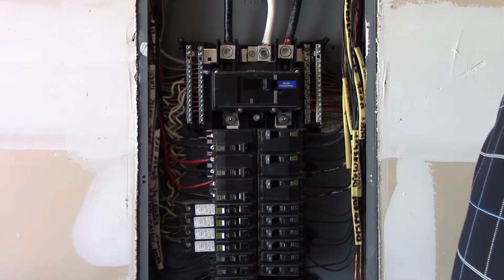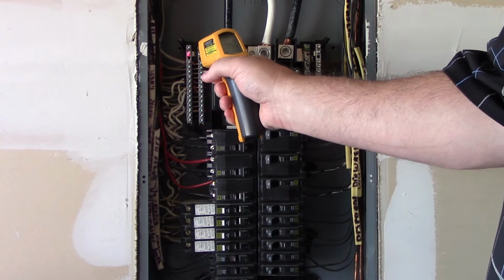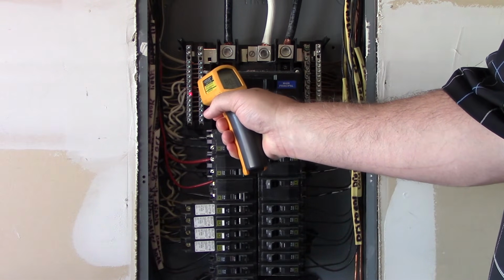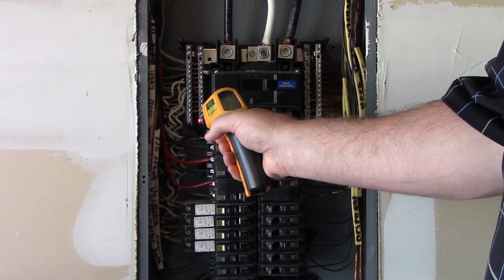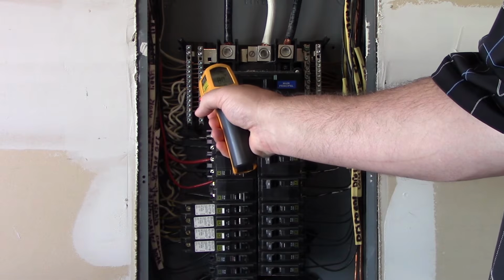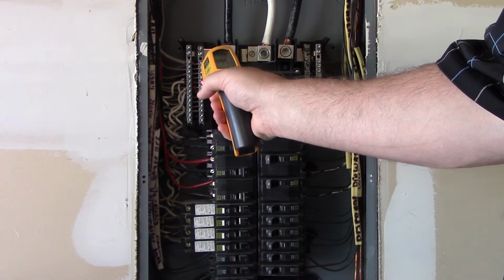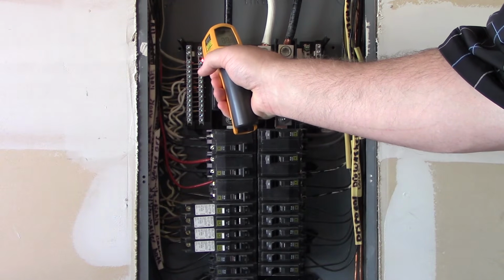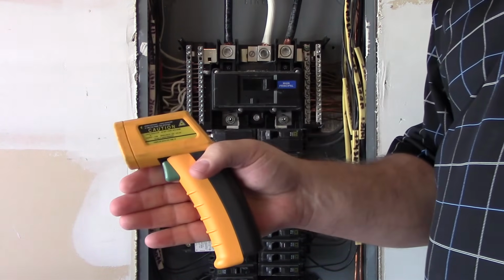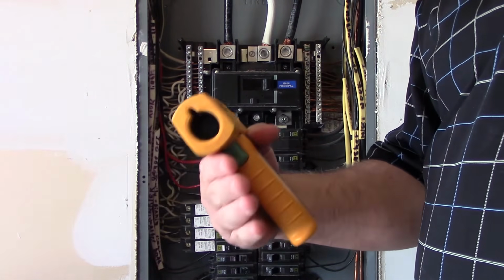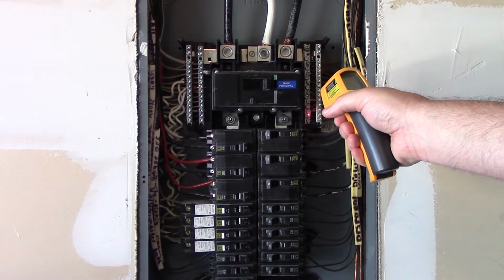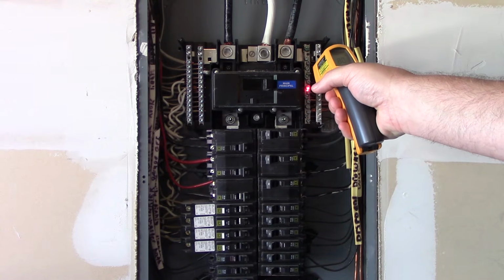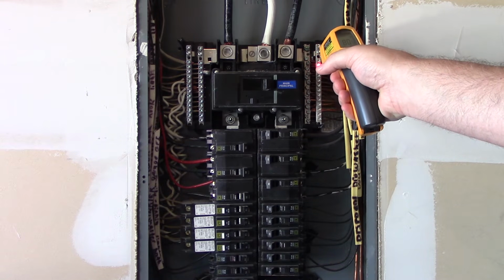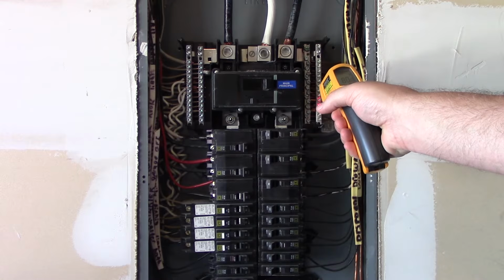One thing I like to do is shoot every one of the terminals for the grounded conductors. I shoot them here and move down, getting a baseline. I want to see if I'm showing any loose connection or any heat that might be building up in here that I can't see, bolted into the actual screw itself. It looks like everything here is about the same. Again, what I'm looking for is any abnormality, anything that's not the norm. I've set my baseline, and now I'm going to come over here and do the equipment grounding conductors as well, just to test and see. Again, all of these are about 80. Everything looks good. Everything looks the same.